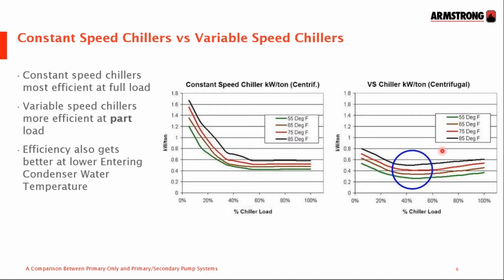Whereas a variable speed chiller has the same efficiency at full load as the constant speed chiller, but as the load reduces on the chiller, the efficiency goes up. The amount of kilowatts of power input required to generate that ton of cooling goes down. More or less, a variable speed chiller will be at its most efficient at slightly under half load, maybe about 40%. So armed with this information, and one more thing, we'll get into the chiller pump slides. The other thing to point out is that the efficiency of the chiller also depends upon the temperature of the entering condenser water into the condenser from the cooling tower. This black line here is the typical 85 °F entering cooling water temperature, which is in many parts a default number.